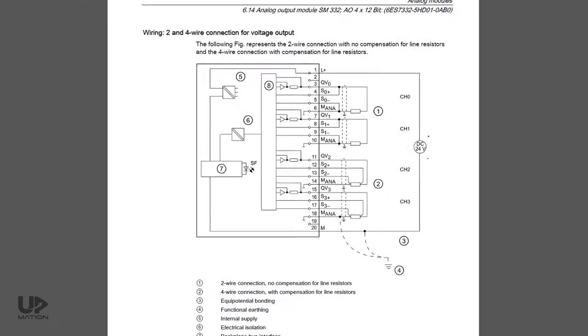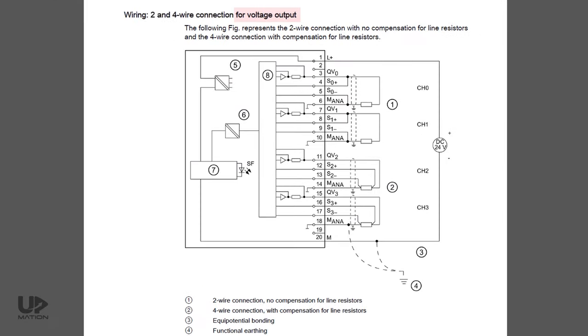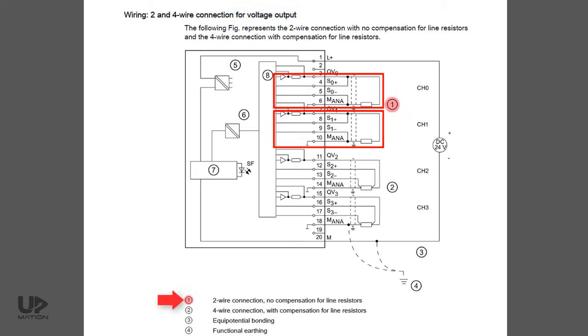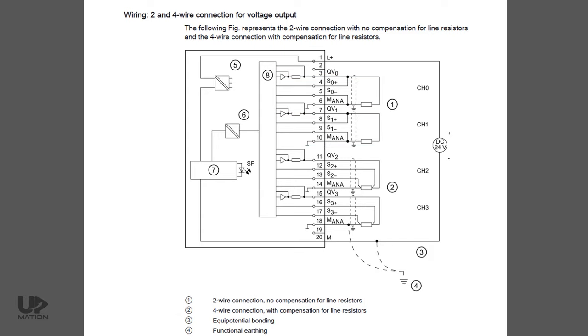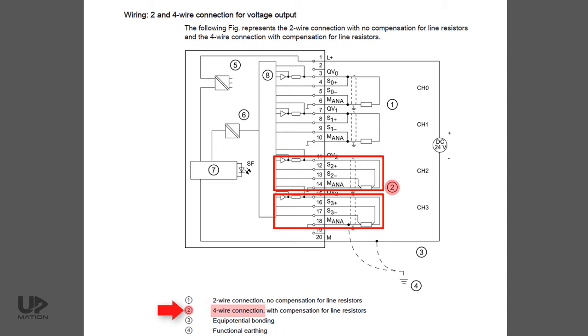We've configured the card for the voltage output. Then, according to the manual, the first 2 channels of this card are for 2-wire connections with no compensation for the wire resistance. In this case, you should connect these 2 connections to each other at the PLC card. Channels 3 and 4 should be used for 4 wire connections.